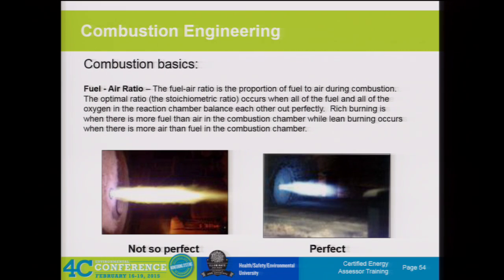By looking at the flame, in general these long orangish flames are an indicator of poor performance—the air-to-fuel ratio is off and we're not getting the most efficient combustion setup. As the boiler air is adjusted, we're able to find a sweet spot where we get that blue-green type of flame pattern. That's what is the ideal situation from a visual standpoint to get a feel for whether we're getting close to having a more efficient combustion process.